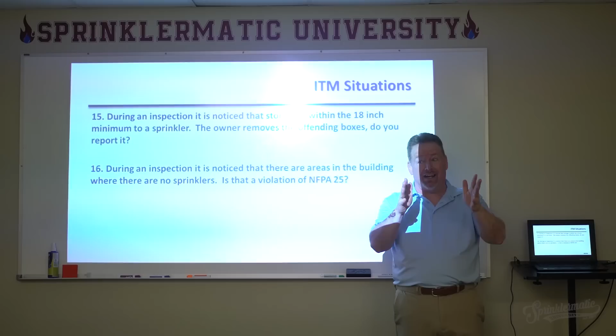The tripping point here is that you know something's wrong. Yeah. The inspection technician is going through going, this is not right. But there's nowhere in NFPA 25 to cite it. There's nowhere in NFPA 25 that says that there are no unsprinklered spaces in this building, or there are unsprinklered spaces in this building, and therefore it's a violation. It's not there, okay? Because it's a design issue. Now, the way you typically handle this, is this a violation of 25? No. Is it a concern?